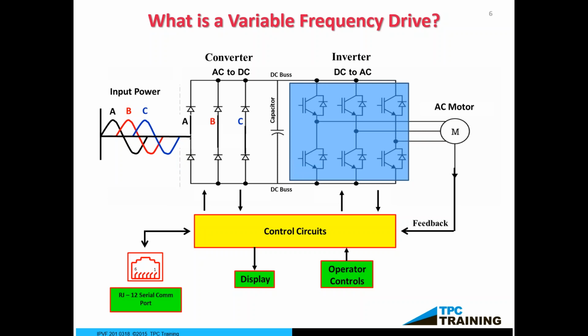We'll be able to interrogate this particular system, whether it be an Allen Bradley, an ABB, a Cutler Hammer, whoever the manufacturer is, we'll be able to go through your particular drive and see how the health of the machine is doing, whether it's input voltage, output voltage, current, torque, acceleration, deceleration, rotation, and a variety of other parameters. So using the display is very, very important.